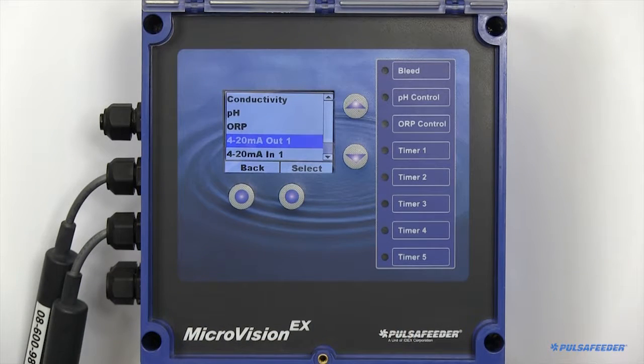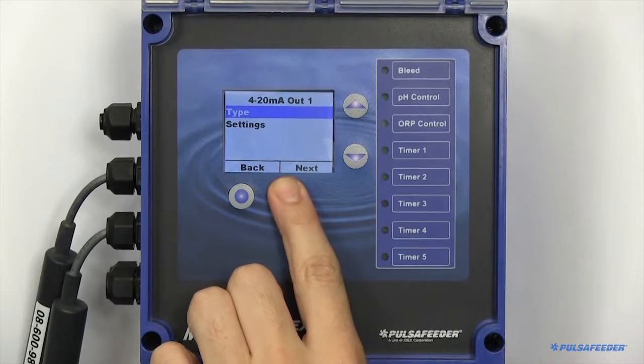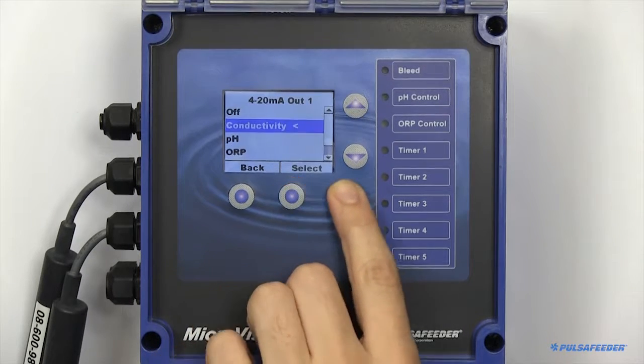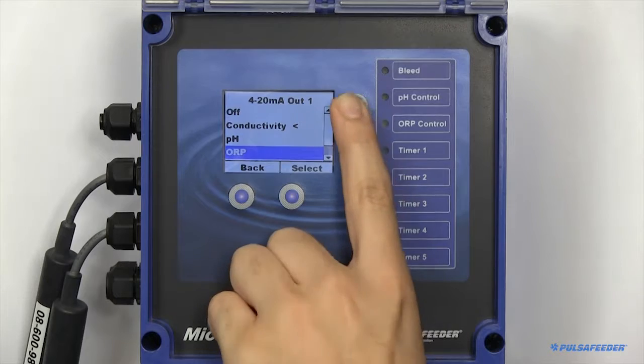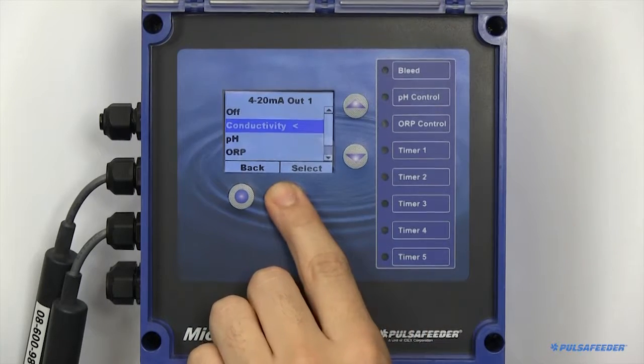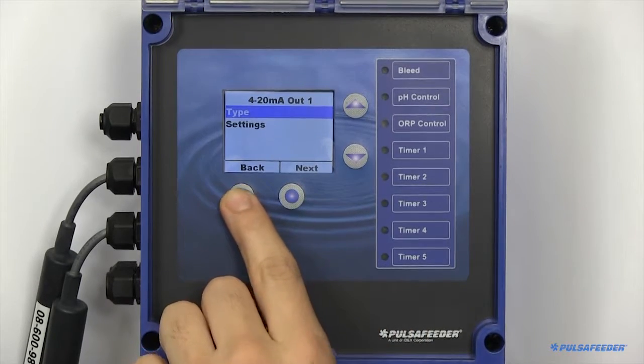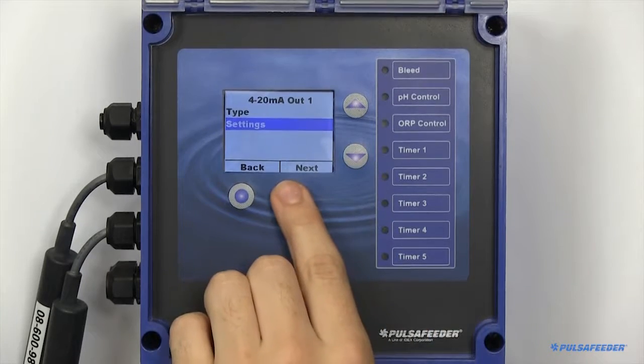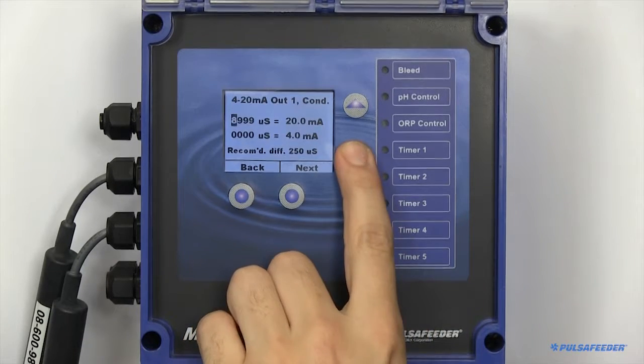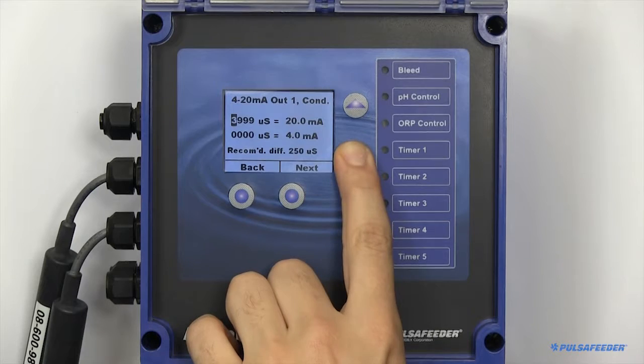To set up a 4 to 20 output board, you will first need to configure the type. After setting the type, go to the settings page. This is where you will scale the reading. Here you can tie the actual probe reading to a milliamp value.